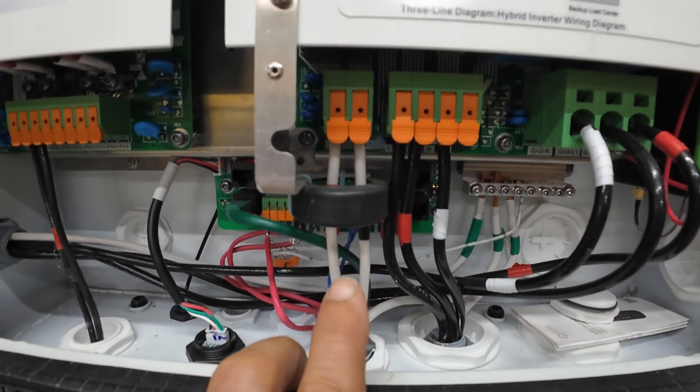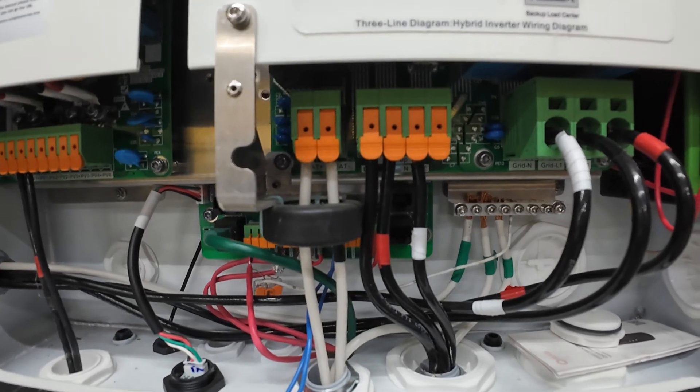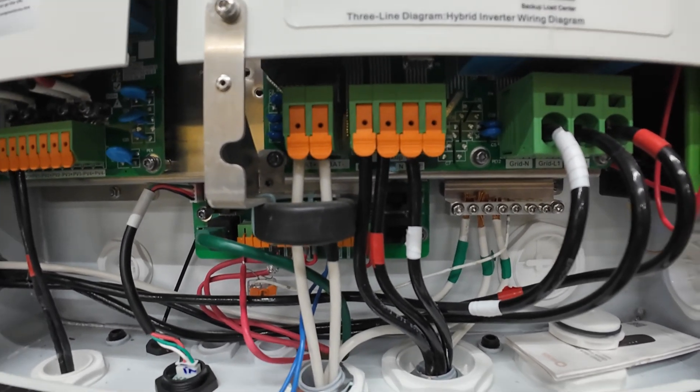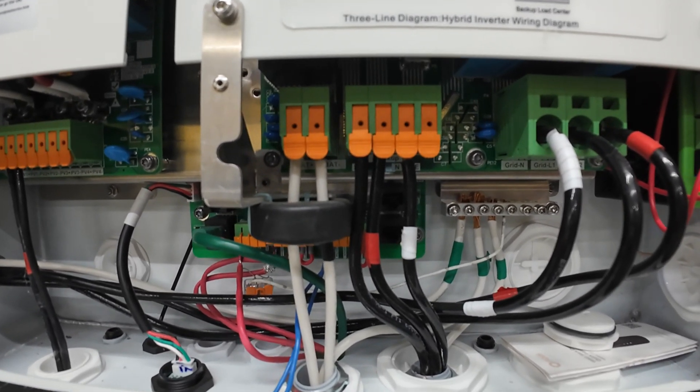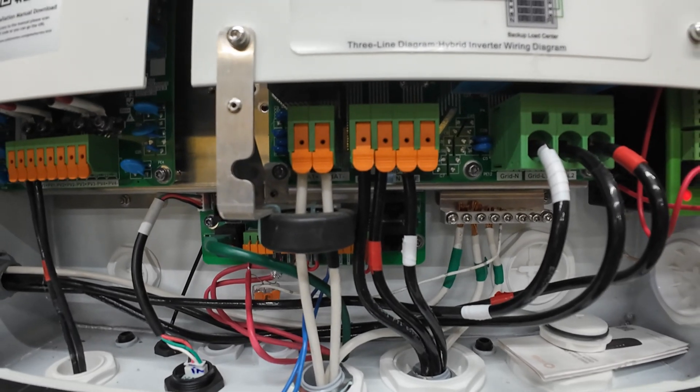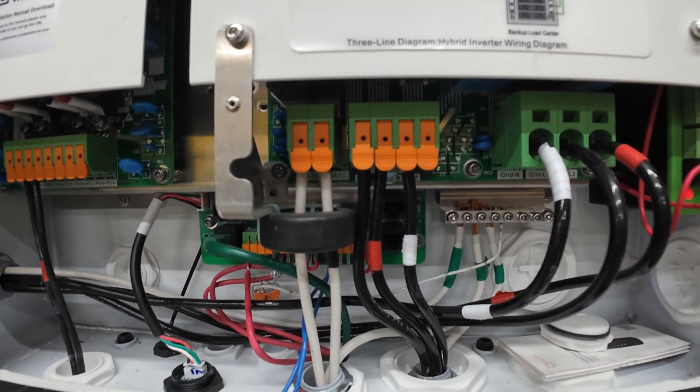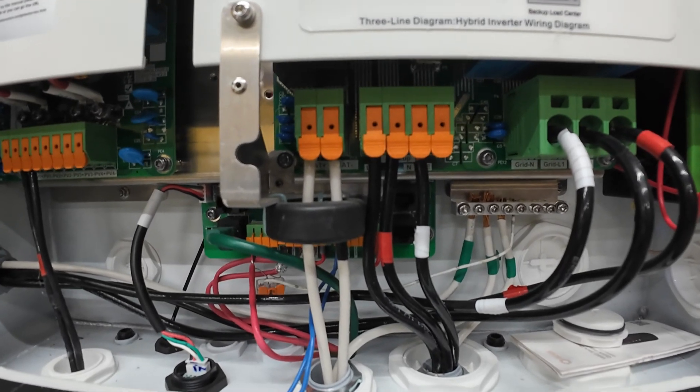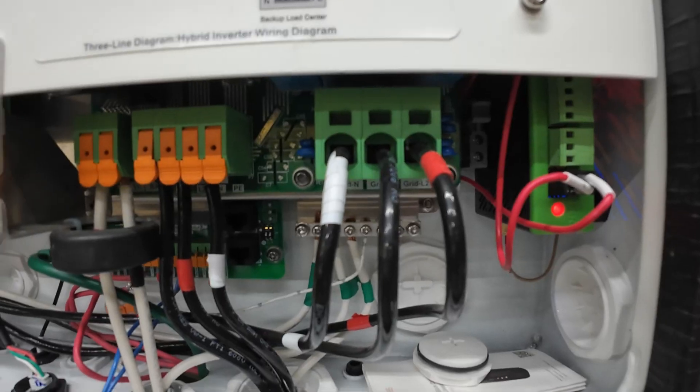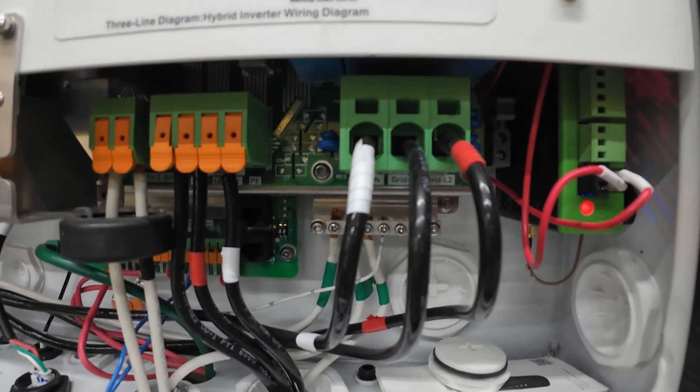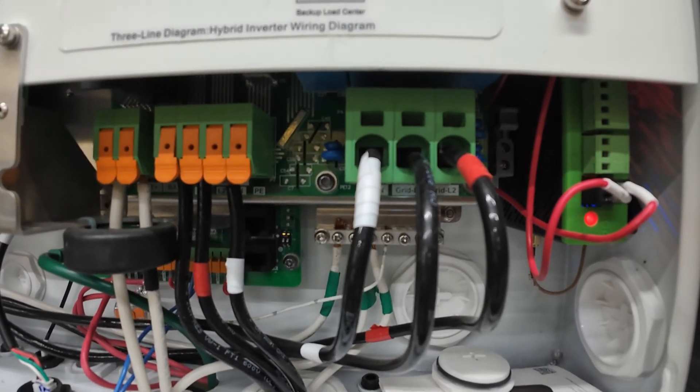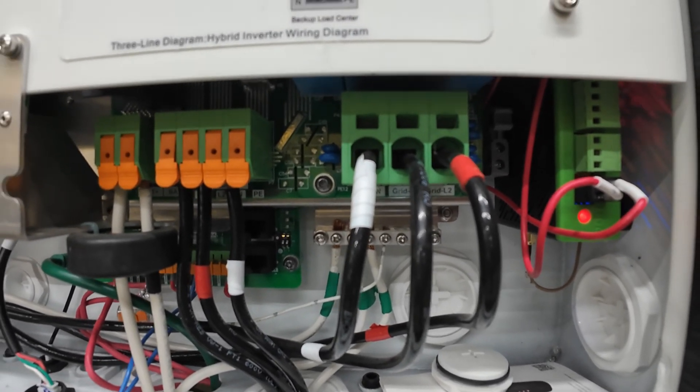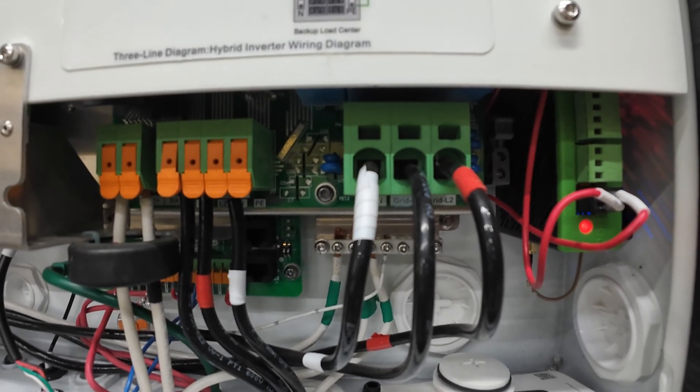Then over here, the white wires, that's your battery. Next to the battery is the backup port. On this inverter, that's where the AC power comes out of the unit when it's in an off-grid situation or when it's in backup mode when it's on-grid. And then over here are your grid connections. That's where you tie into the grid, if you have a grid. If you're off-grid, that's going to be your generator connections.